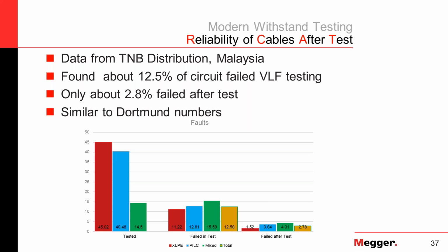And what Mr. Mo pretty much said in this paper and this publication is that this should be avoided at all costs. It's not comparable, because the failure rate after testing of all the circuits that hadn't been tested at 0.1 hertz was much higher. Actually, this is also the only international study, really, that has a significant impact and that ever looked into details between the frequency. So it's the best we got.